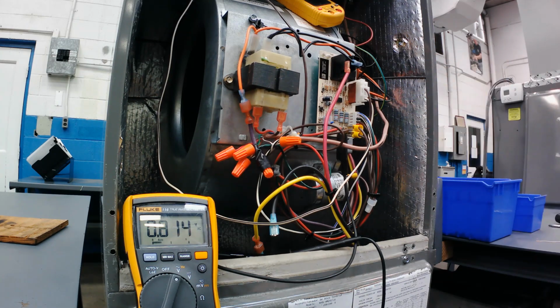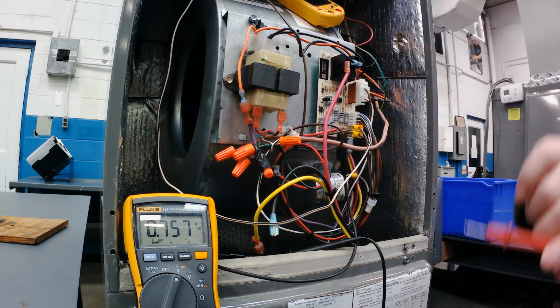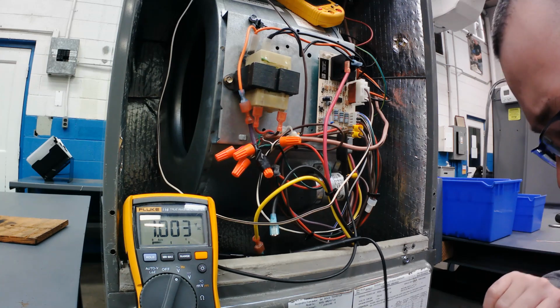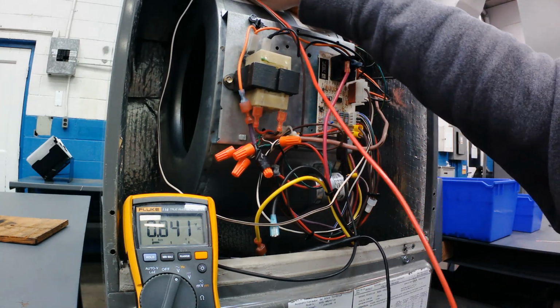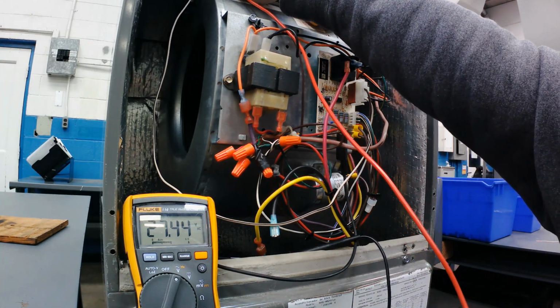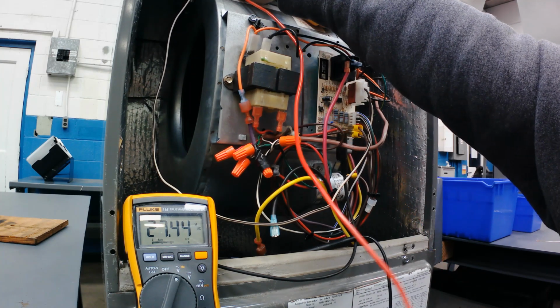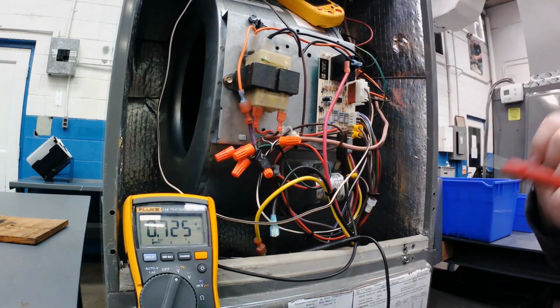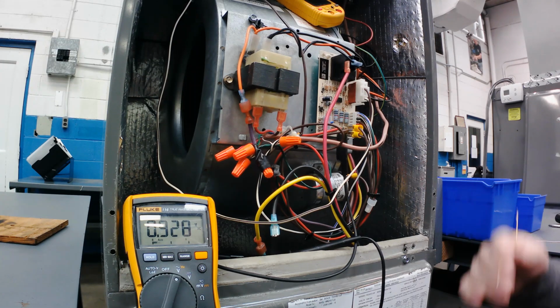I've got 27 volts. I could easily go up top to the heat sequencer or heat relay and check where the actual white wire went into that particular coil. I've got 27 volts. So that's part of your troubleshooting there. All right, and that's pretty easy.